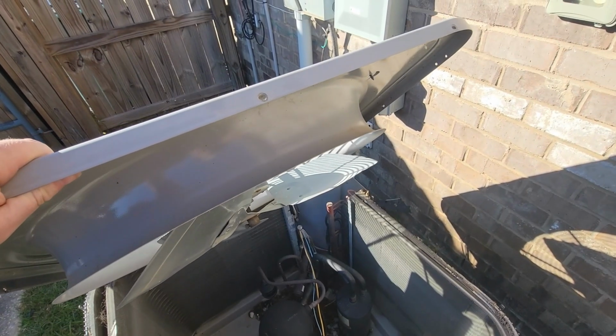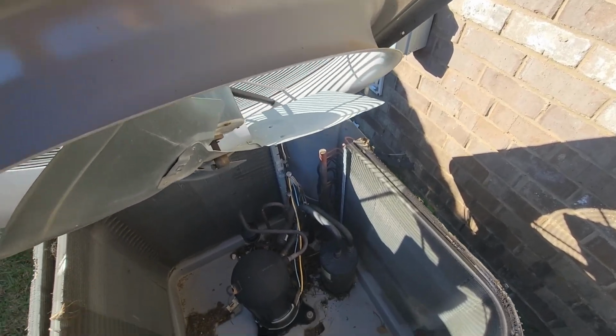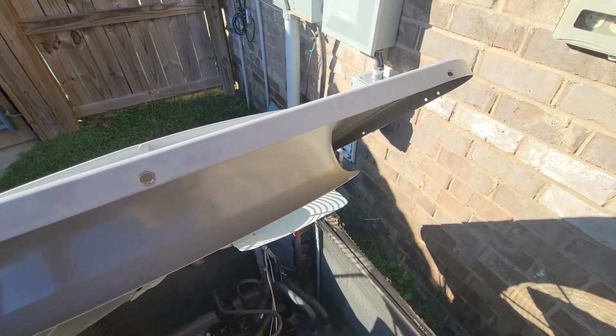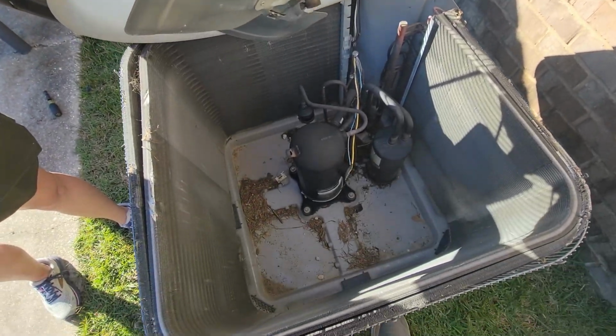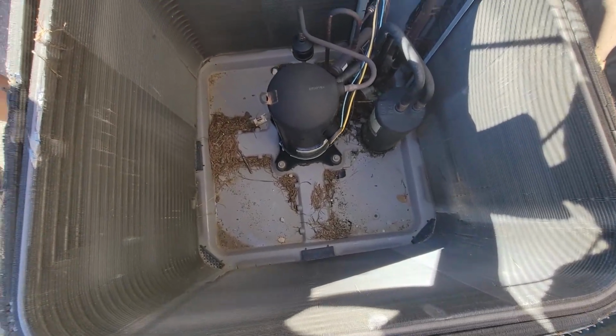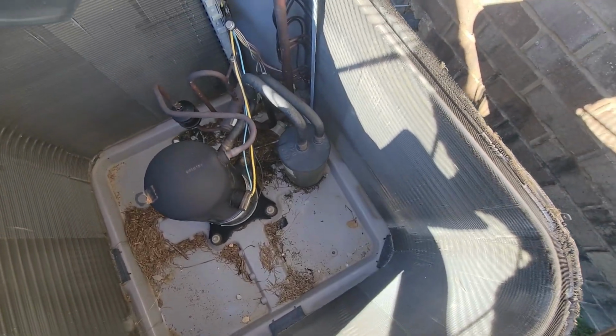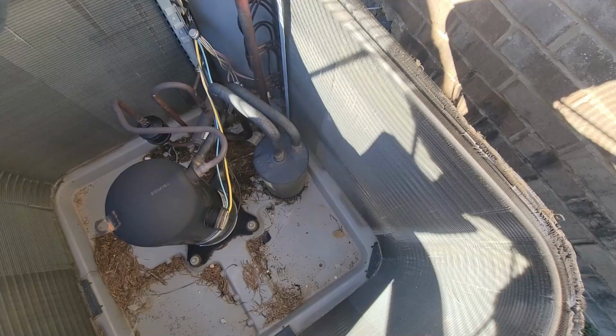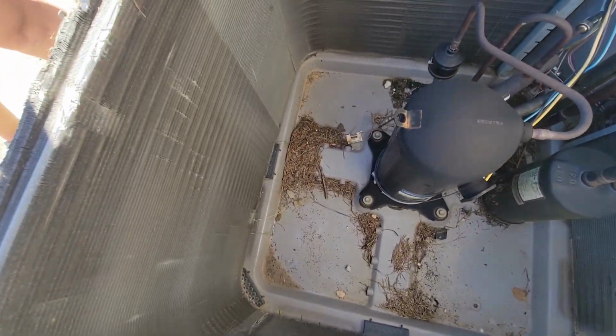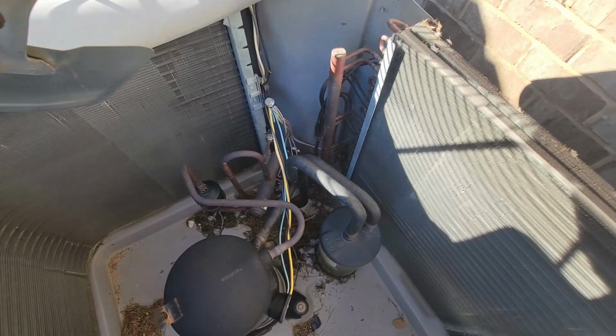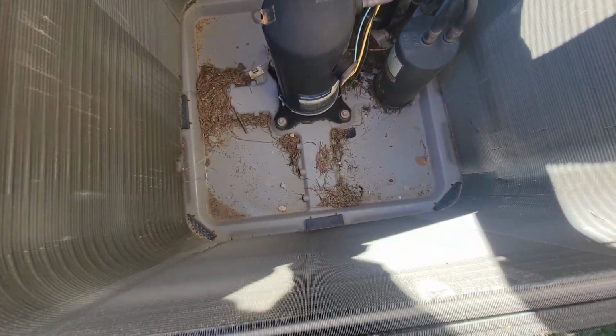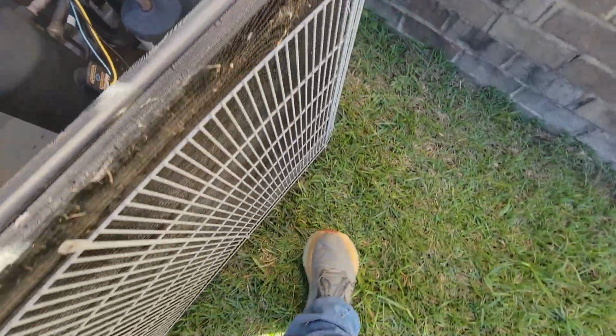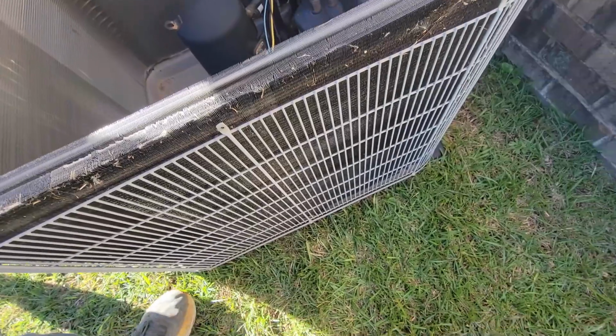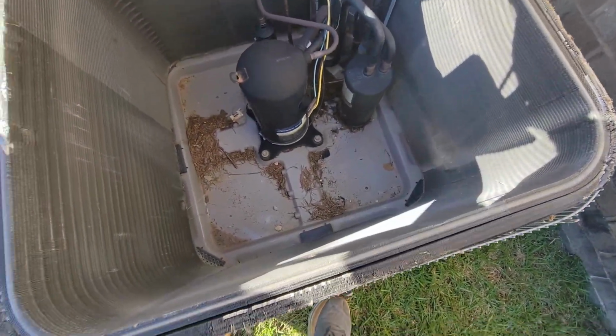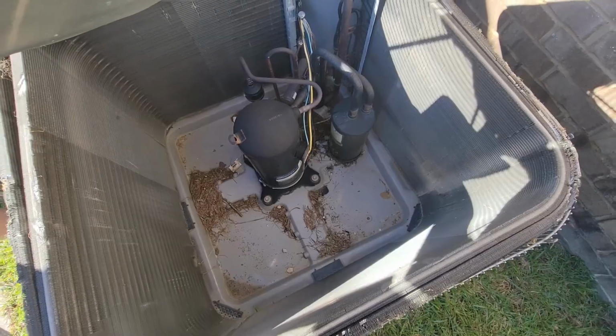Okay, the next thing you're going to do is come around. Now, some people just remove the fan, but I do not, because I don't want any imbalance in the fan. So I've removed the top cover and I'm propping it up. Get yourself a partner - I've got my wife - and we're going to clean out everything on the inside. Look at your wire connections really good, make sure nothing is overly corroded, and then wash out these radiator fins, making sure there's no dirt or debris stuck in them. They make a little tool in case somebody's come through and kicked them shut, to straighten the fins back out. You don't want them pushed in - a lot of kids like to come by and push on them - but they do make a tool that will fan them back out. Ultimately, what you're doing is coming in here to do an inspection and clean out all this dirt and debris.